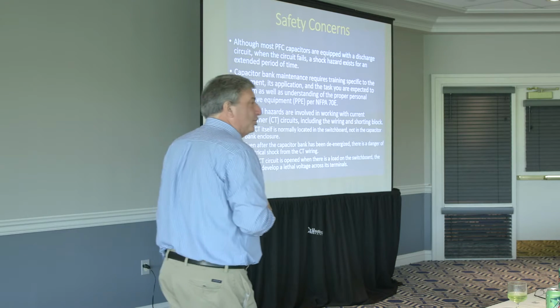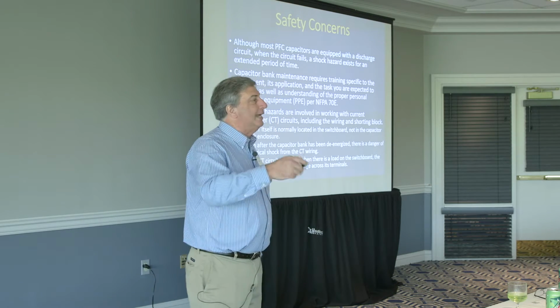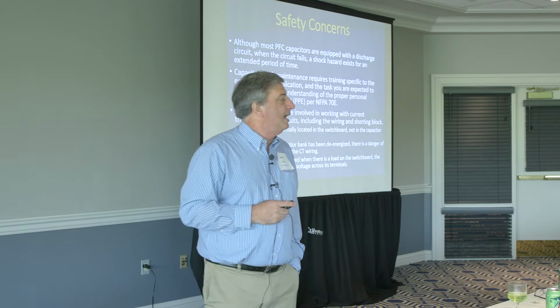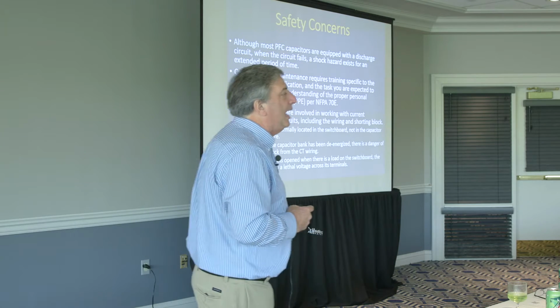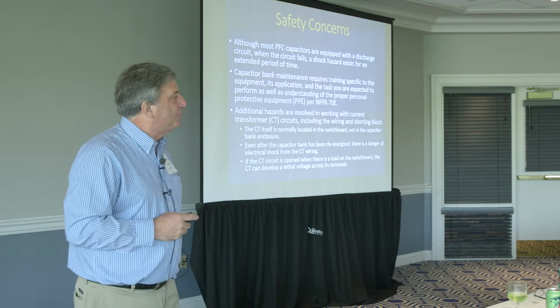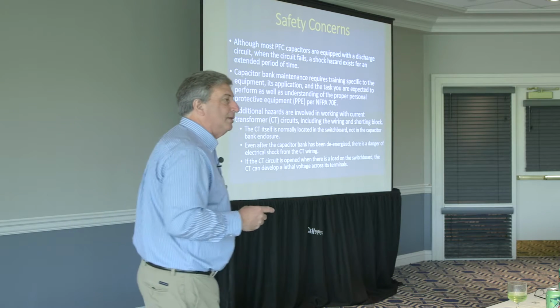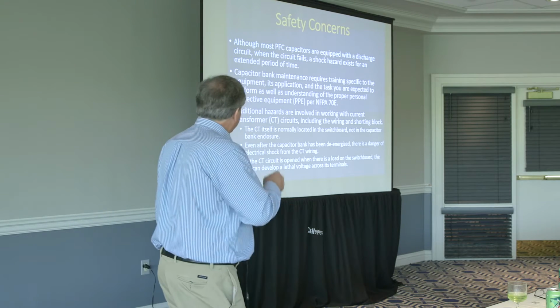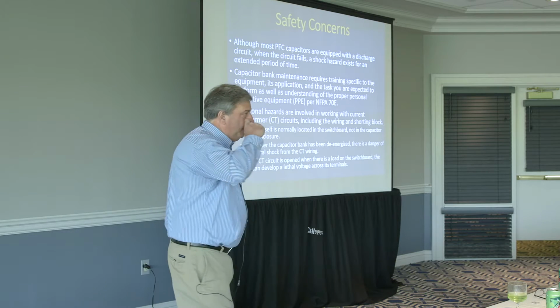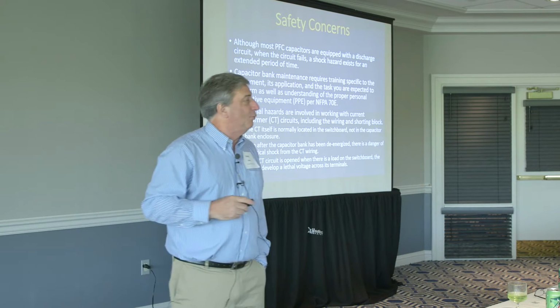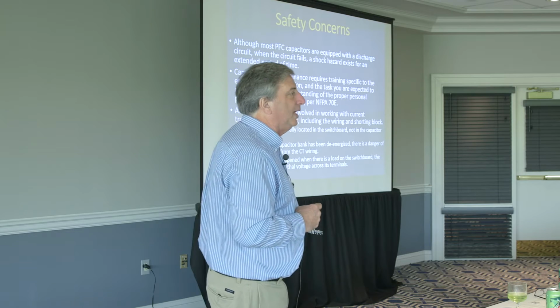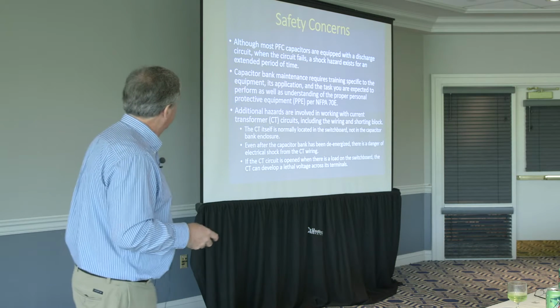So people just assumed there was a discharge circuit and it would work. But it had not been maintained, it had failed, and so when they made a faulty assumption like that, bad things happened. And typically we get that capacitor then feeding into the others or something that wasn't expected, feeding to the wrong place, and somebody gets hurt.